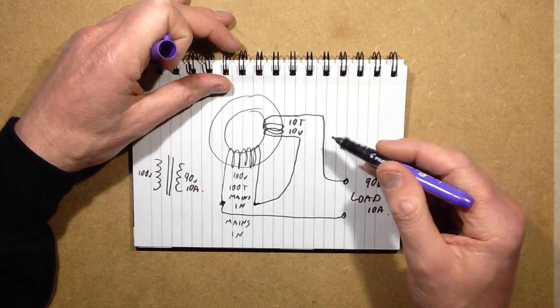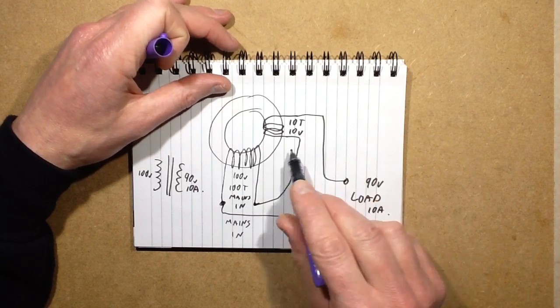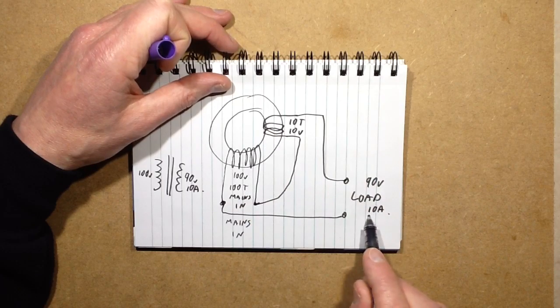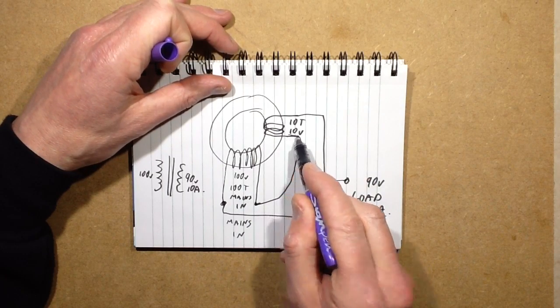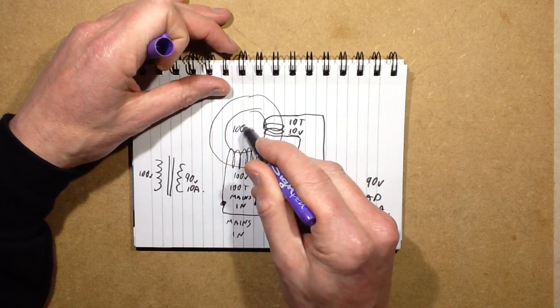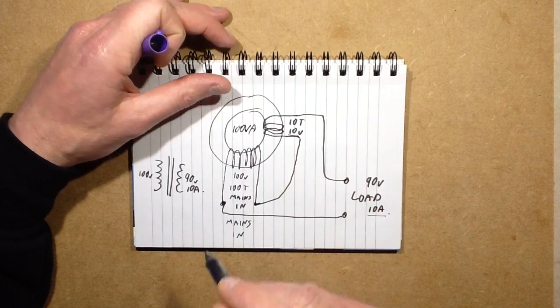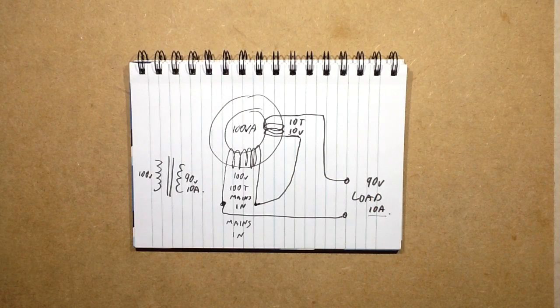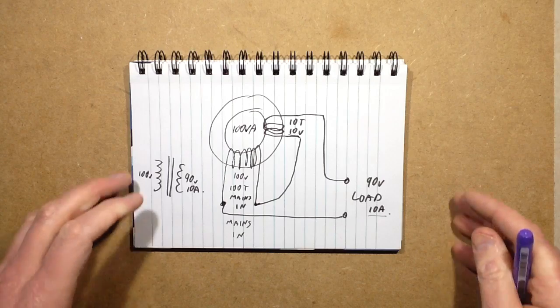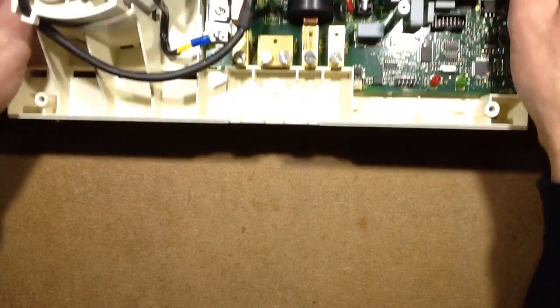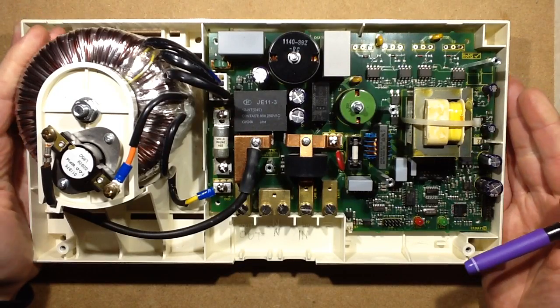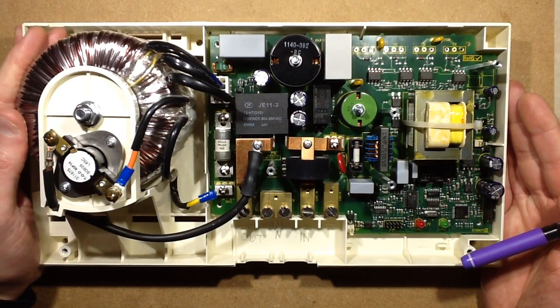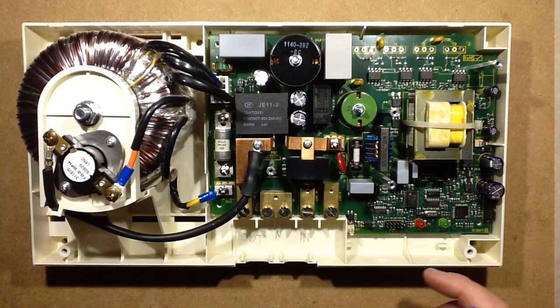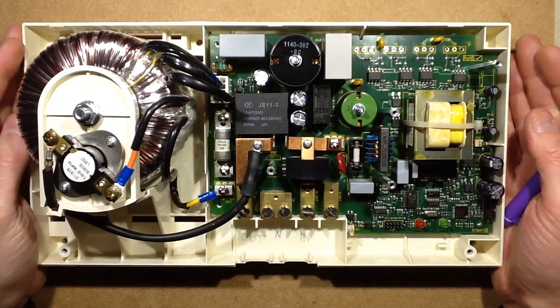And because this secondary coil here is only seeing the 10 amps at the 10 volts, the transformer only needs to be rated 100 VA, 100 watts, 100 volt amps. So that's the principle of a buck or boost transformer. And that's pretty much what they've done here in a way, except this is designed to lower the main supply from 230 volts apparently to 220 volts. And it's quite an invasive unit. It's not subtle.